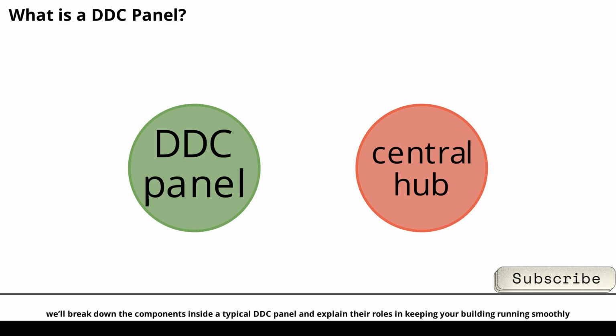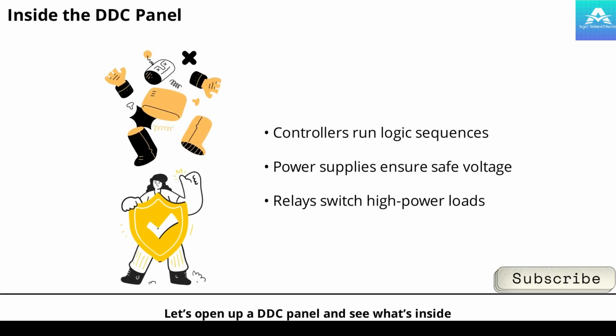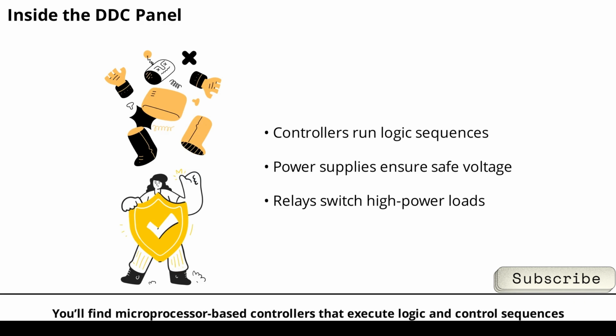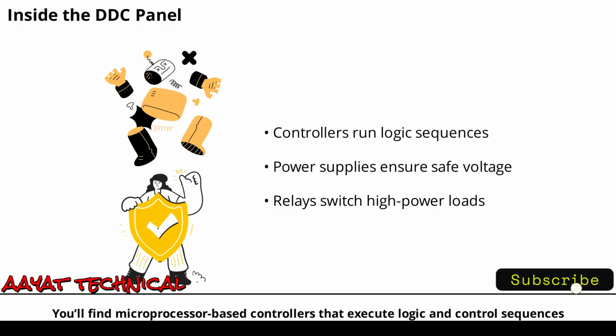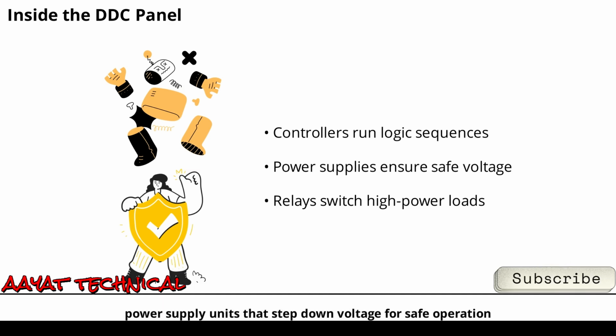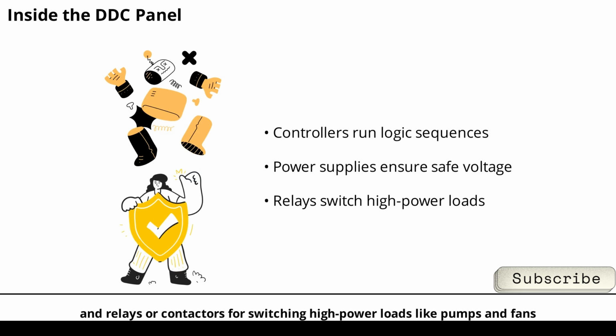In this scene, we'll break down the components inside a typical DDC panel and explain their roles in keeping your building running smoothly. Let's open up a DDC panel and see what's inside. You'll find microprocessor-based controllers that execute logic and control sequences, power supply units that step down voltage for safe operation, and relays or contactors for switching high-power loads like pumps and fans.